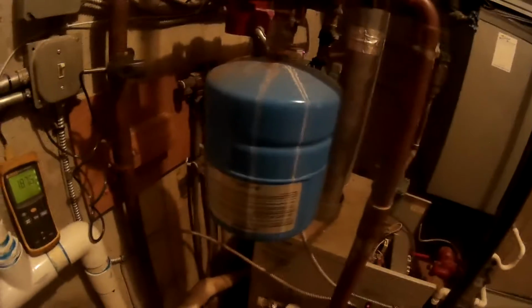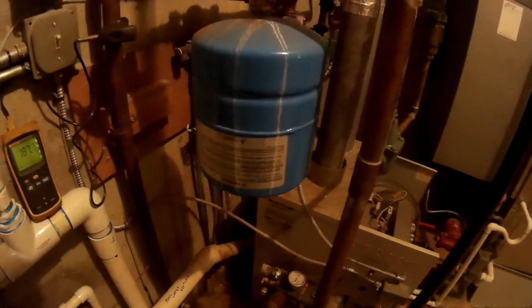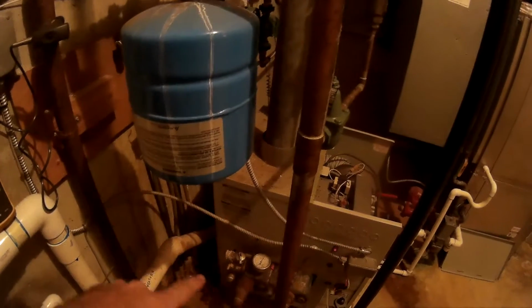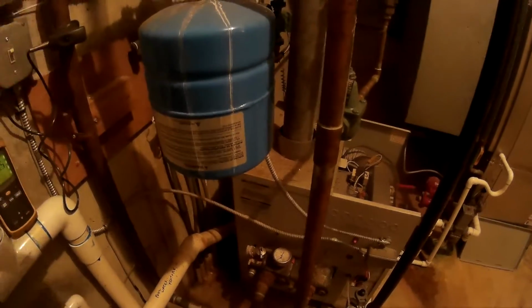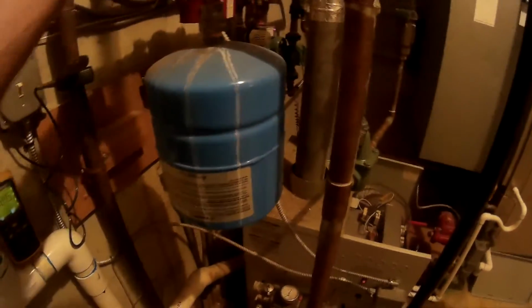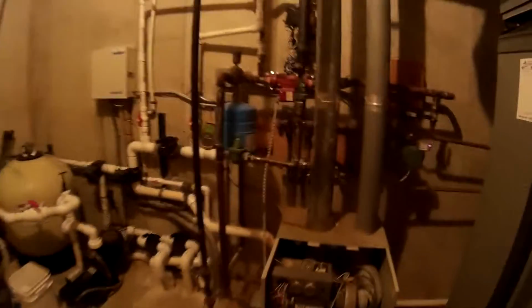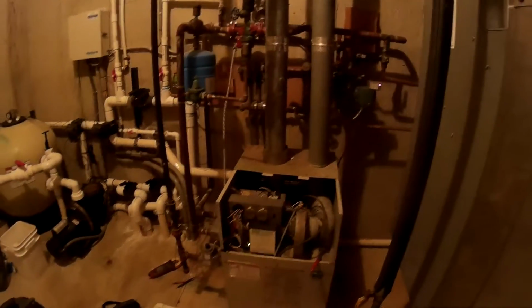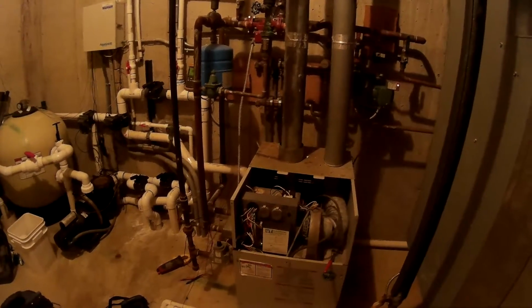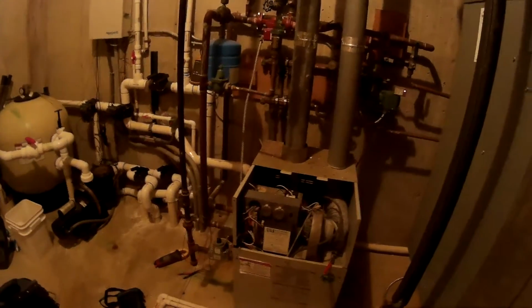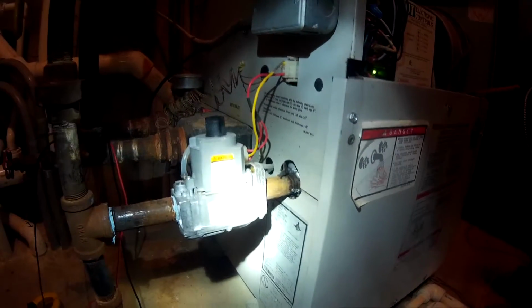So I'll just tell my customer, hey, gotta order parts, get back. We'll replace that operator control, the T&P, the pump. While I get the pump out, I might as well replace the air valve just as a precautionary measure, and clean the inducer motor. So that's it for this one. This is about troubleshooting the operating control on a Lochinvar boiler. This is a Lochinvar Efficiency. It's a little copper fin pool boiler, and the model number is EBN 150.